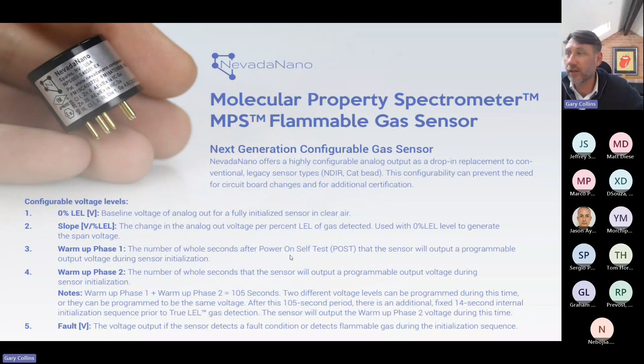If you're looking for a drop-in replacement sensor that can see hydrogen and you don't want to change your circuits, please talk to us. We can share far more information on how we can configure that sensor, and ultimately you can put it in a digital sensor with a configured analog output to meet your circuit needs. We've got a lot of experience in that area, and certainly when you look at hydrogen and having something where you might only have a Pellistor, you could reduce power with the MPS, or if you're using IR, it gives you access to measuring hydrogen as well. So please don't be shy if you want us to look at configuring that for you. From a digital output perspective, as I said, here on the left shows you that we can give you the gas reading. So the traditional gas, what is the LEL value?